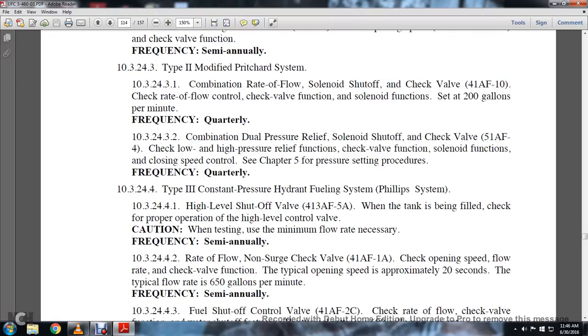Alright, Type 3 constant pressure hydrant fuel system, or the Phillips system. The high-level shutoff valve: when the tank is being filled, check the proper operation of the high-level control valve. Caution when testing the minimum flow rate necessary. Frequency semi-annually.